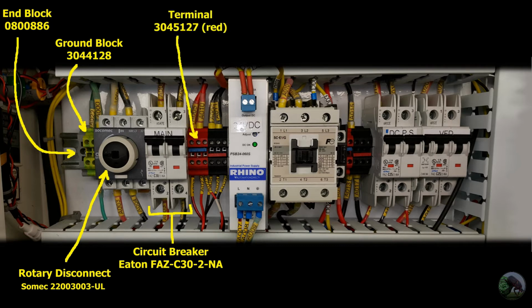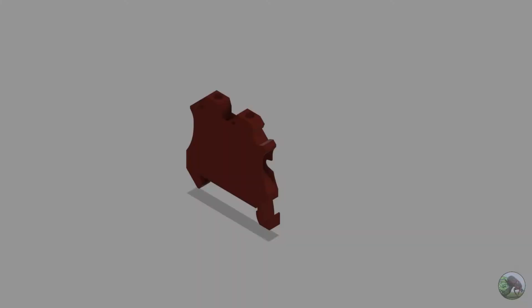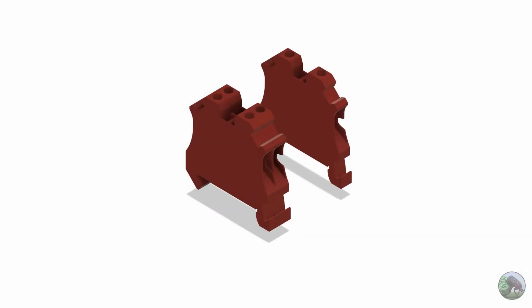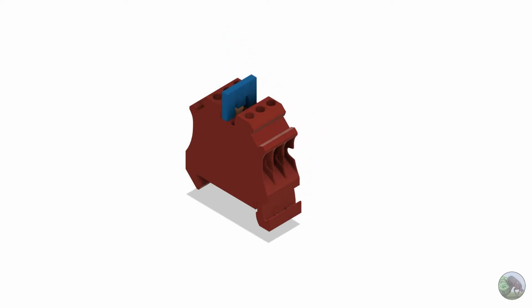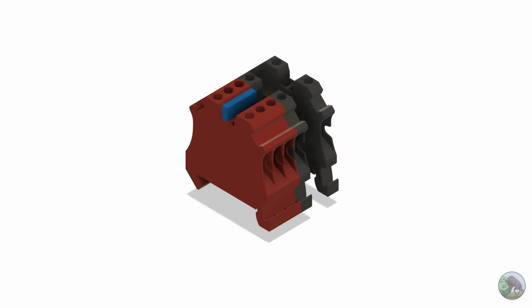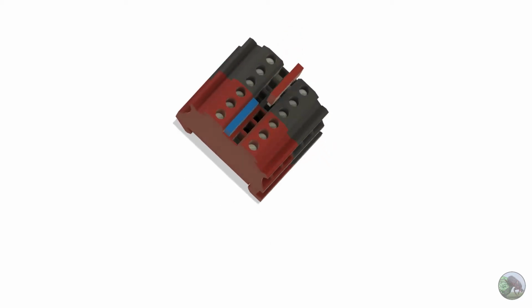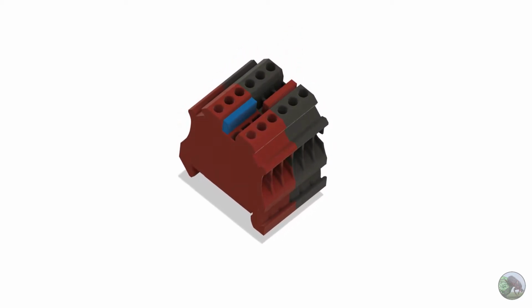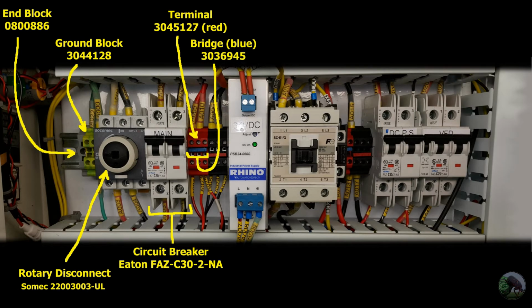Next up is these red terminals. So these are just through terminal blocks, so it just connects one side to the other, and these three are bound together using that little blue bar, which is a bridge. So I just wanted to make this a little clearer. So here's a little animation of these blocks. So the terminal blocks go together, and then this bridge goes in and binds them together. And so here's the black ones coming together, and then they get bridged together. So it's a pretty important and common feature of these terminal blocks to understand. And the reason I chose blue was just to make it more obvious to anyone looking into the box that those three terminal blocks are bound together. So it basically means, visually and continuity-wise, that all the wires coming into that red block, all three of them, are connected together. And so that's what that bridge does.